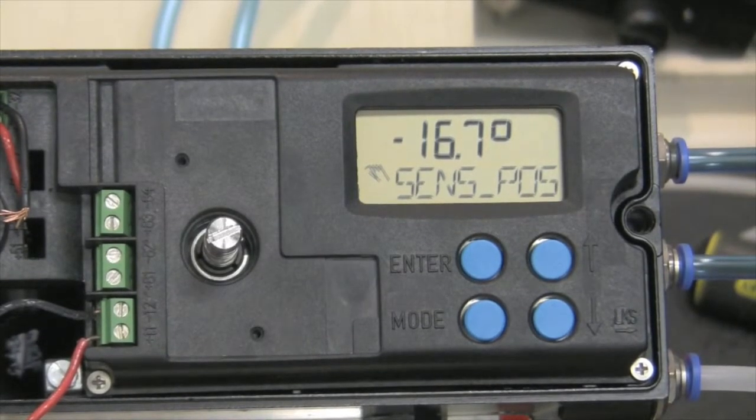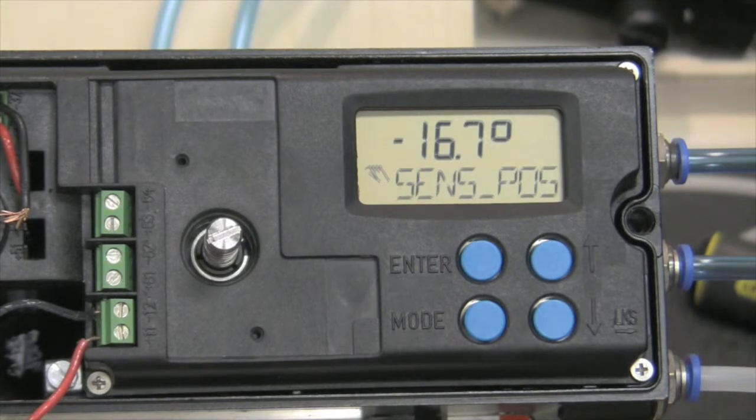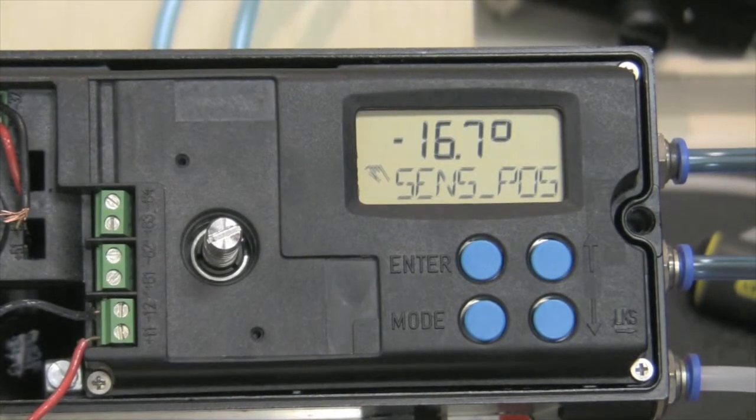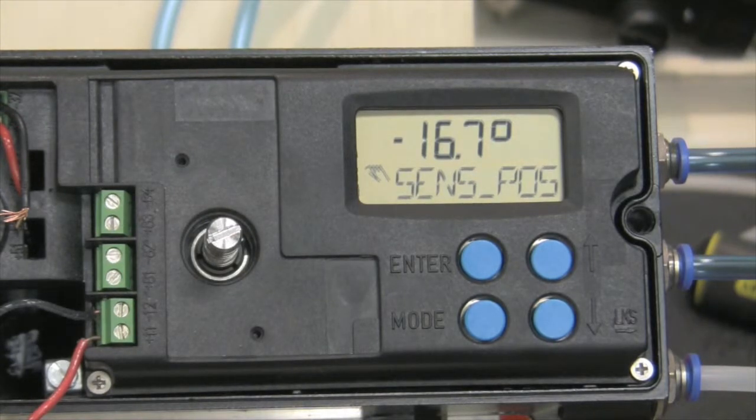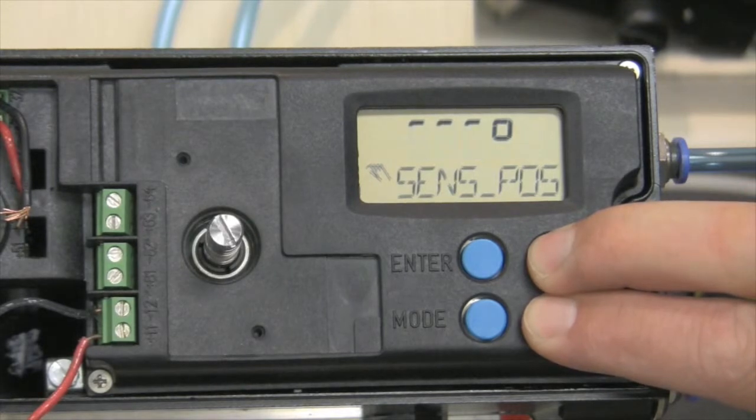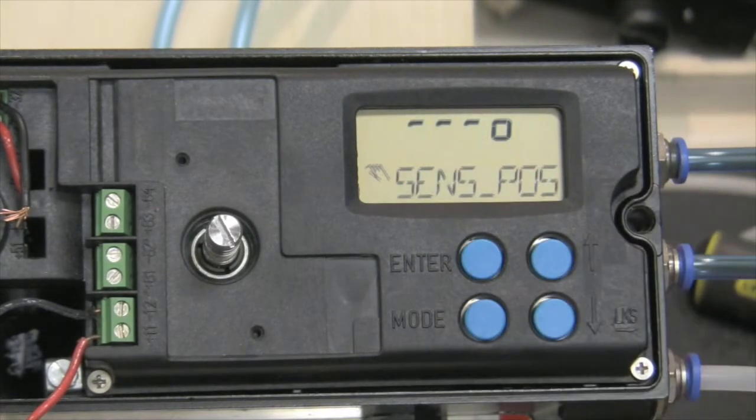We want to show you an example of an error message that you would get when you try to calibrate the positioner when it's out of quadrant. As you can see, here it's listing a number of negative 16.7. When we go to stroke it, it obviously reads a non-number, which means it's way out of quadrant.